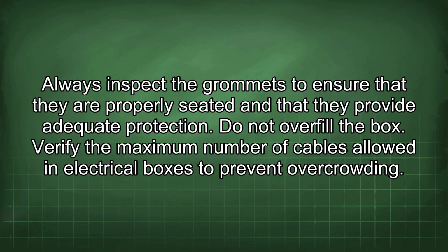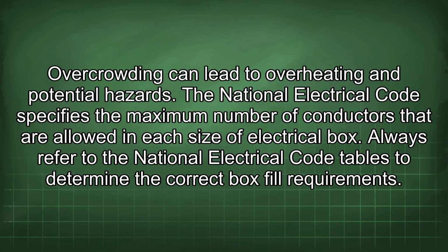Do not overfill the box. Verify the maximum number of cables allowed in electrical boxes to prevent overcrowding. Overcrowding can lead to overheating and potential hazards. The National Electrical Code specifies the maximum number of conductors that are allowed in each size of electrical box. Always refer to the National Electrical Code tables to determine the correct box fill requirements.